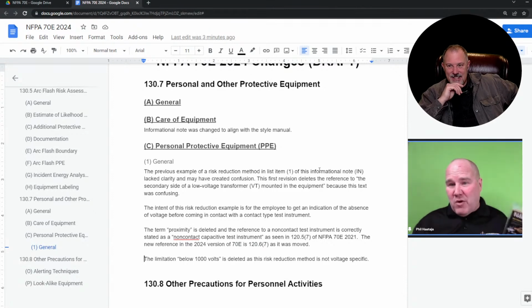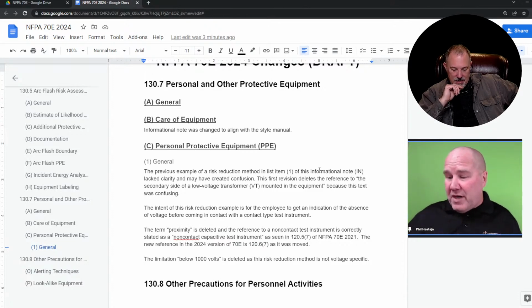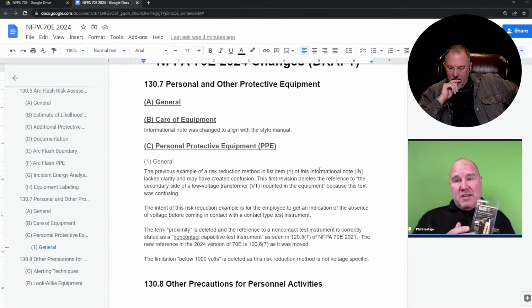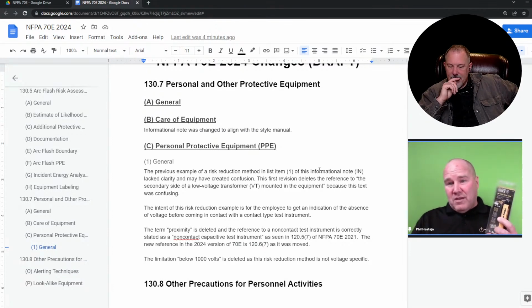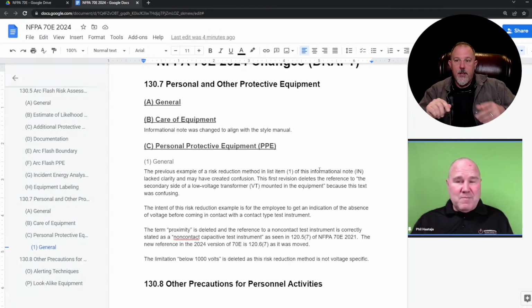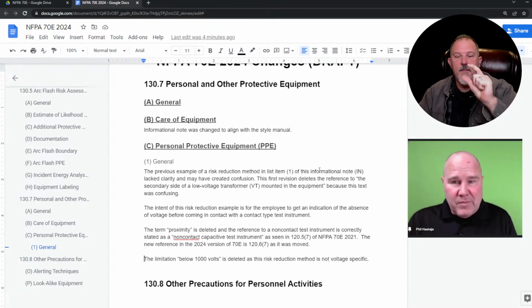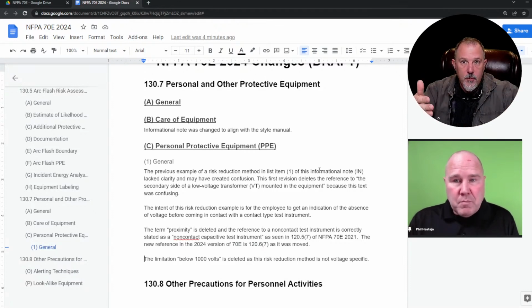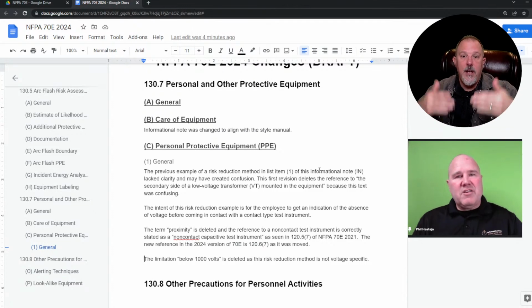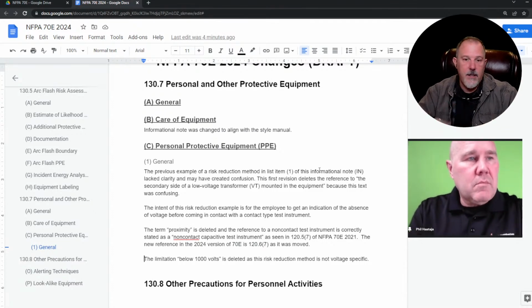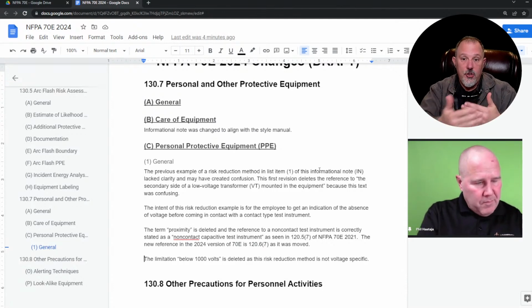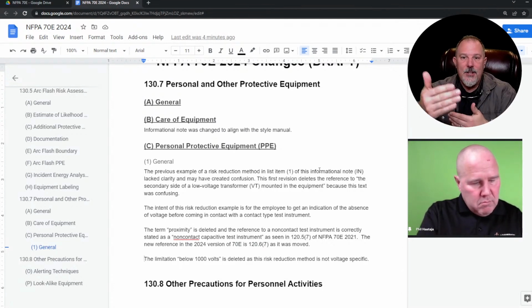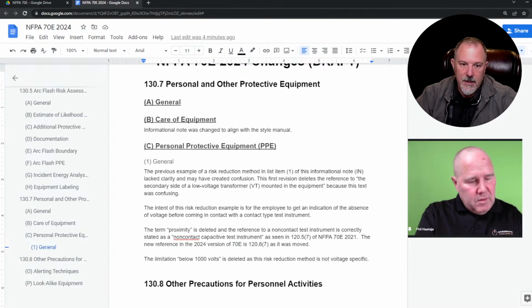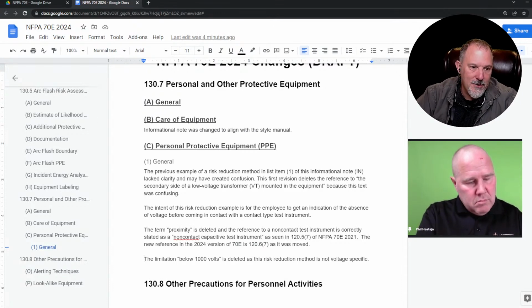I always get some chuckles, but somebody will argue with me, and I go back to this, 120.6(7), and say you cannot use this to create a safe work condition, and you can't do it. Yeah, not if you're going to meet the code. That's right. You know what I call that? A layer of the onion. Visible blades is a layer of the onion, those proximity sensors are a layer of the onion, and you just keep peeling those layers away. The more layers you put, the less the likelihood that you're going to have a problem. So it's just like anything. That's what I learned that day.